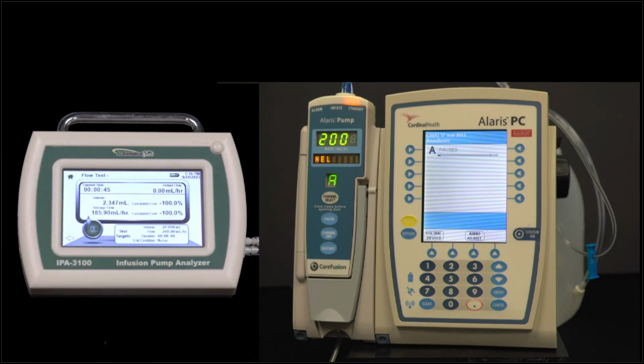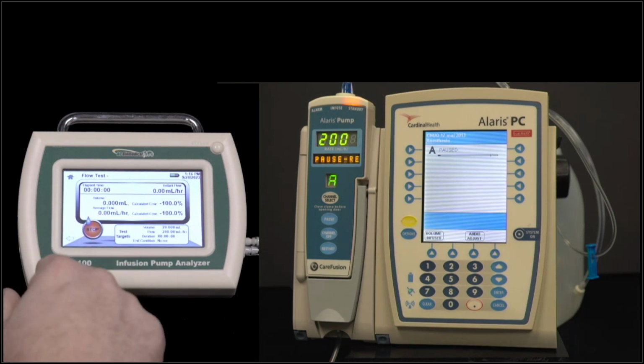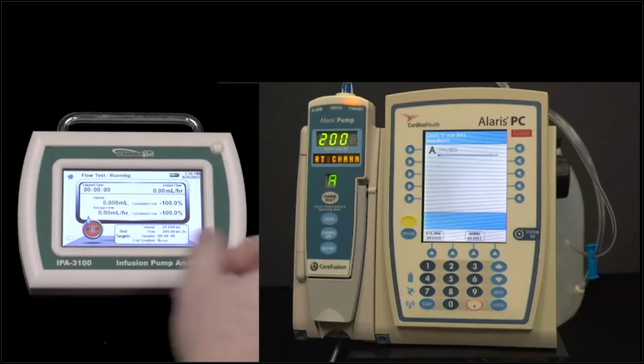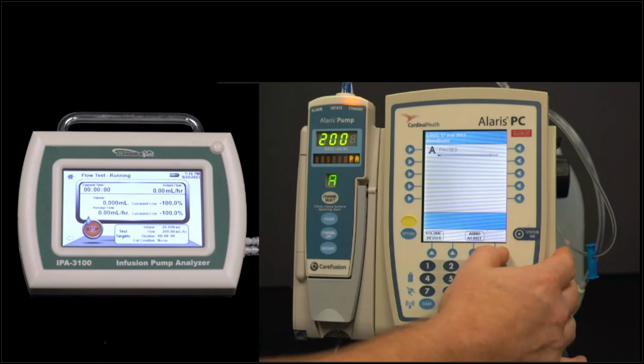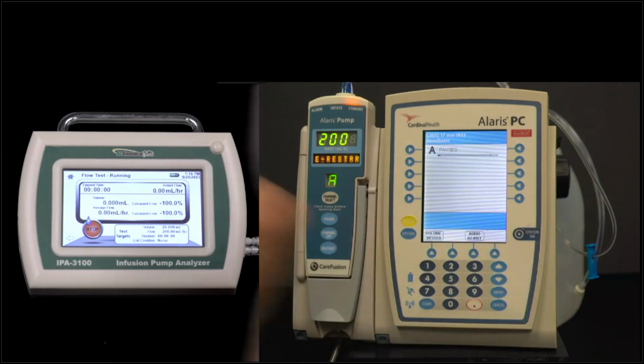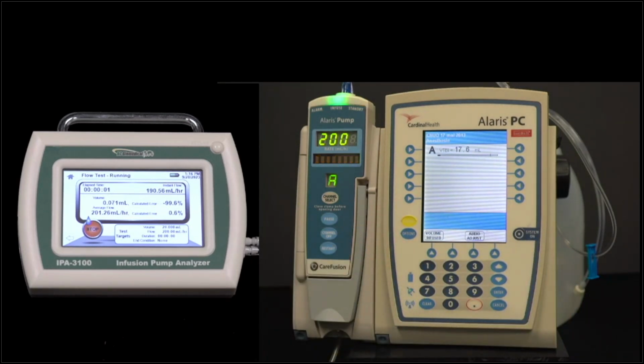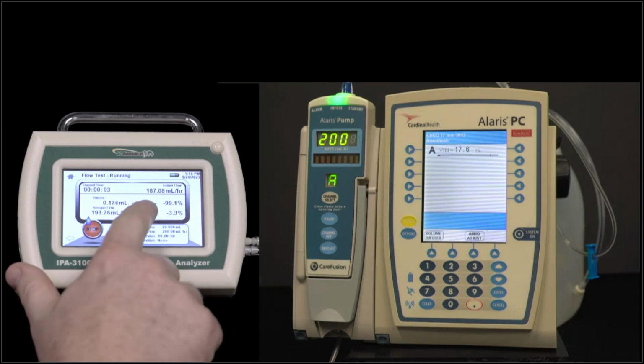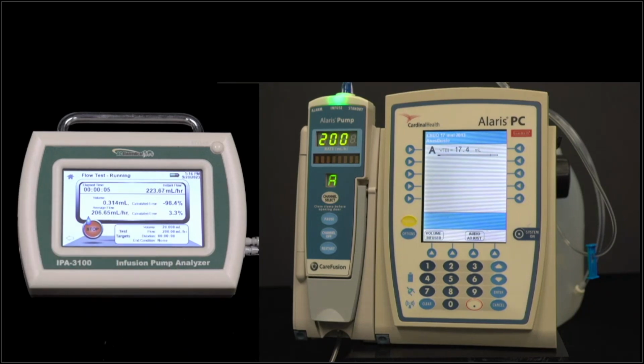I proceed to the test again. I press the start button, and now it's saying the test is running. It's ready to go, and I'll hit restart on the pump. And now we can see we're getting measurements for error in the volume and the flow rate. So those are 2 ways to run your test.